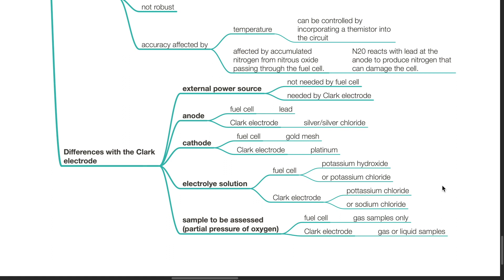Comparing the fuel cell with the Clark electrode: the fuel cell requires no external power source, whereas the Clark electrode does. The anode in the fuel cell is made of lead; in the Clark electrode, it is silver-silver chloride. The cathode in the fuel cell is a gold mesh; in the Clark electrode, it is platinum. The electrolyte in the fuel cell is potassium hydroxide or potassium chloride; in the Clark electrode, it is potassium chloride or sodium chloride. The fuel cell assesses only gas samples, whereas the Clark electrode can assess both gas and liquid samples.